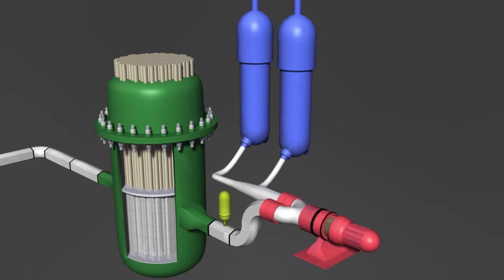In the fission chain reaction, thermal energy is released. Water is needed in order to absorb the thermal energy and keep the chain reaction going. Inside the vessel, the water is heated to over 570 degrees Fahrenheit. The water does not boil, however, since the pressurizer maintains the water pressure constant at around 160 bars.